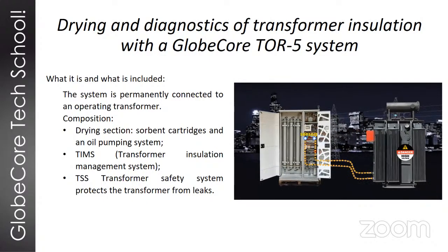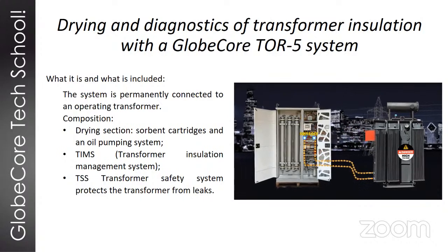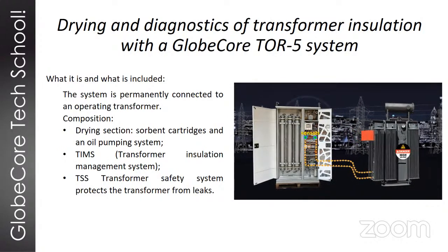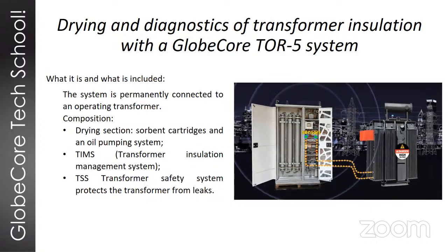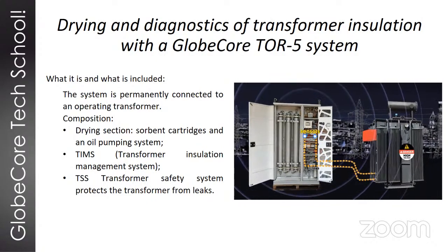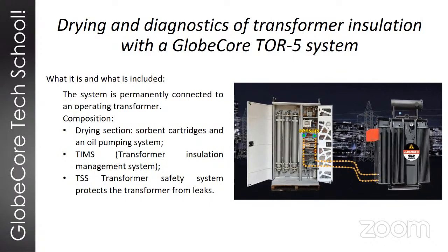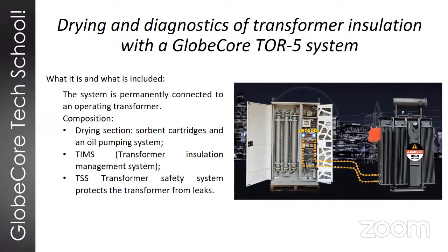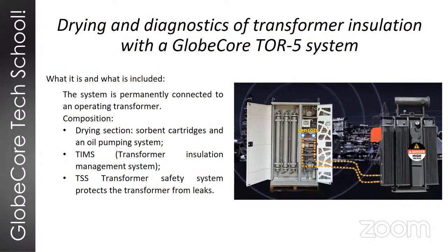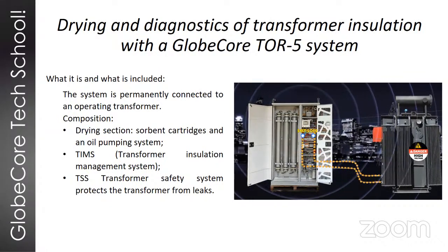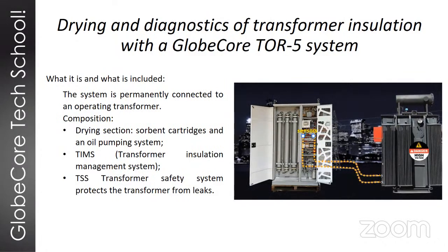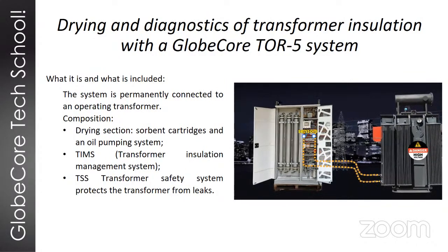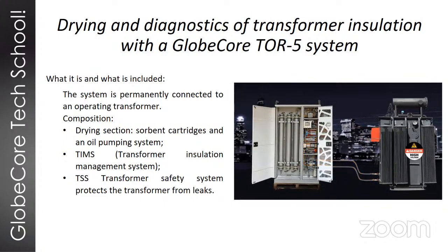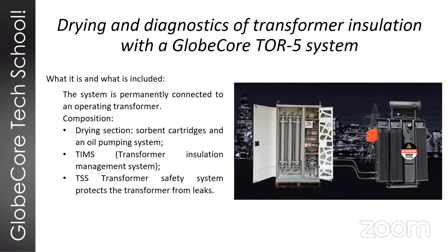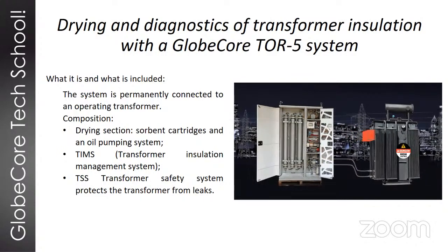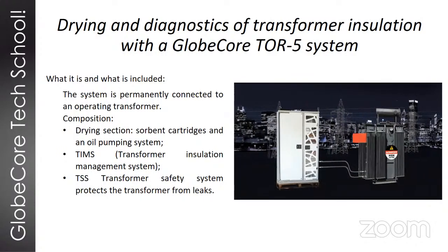One important factor of interaction of the system is that based on the results of continuous oil monitoring, we can see when the oil is aging or when the dehydration process is not sufficient. It's also possible to see that it's time maybe to use a degassing or dehydration system, or even a regeneration system, maybe to bring it in, connect it to the transformer, and process the oil. So if you have this monitoring information, and if you perform the oil processing in a timely manner, degassing or regeneration, that obviously is always good for the condition of your transformer.